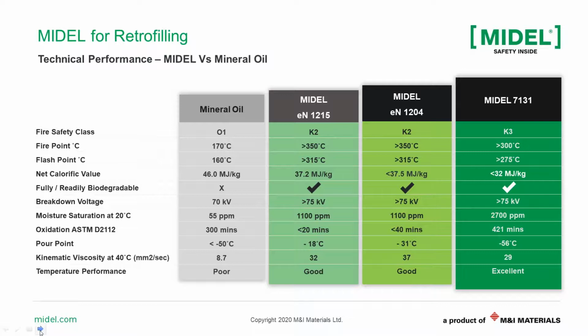The first one, as Steve mentioned, is about the fire safety of the liquids. As you can see on the screen, MIDEL has the classification K2 or K3, which means the fire point of these liquids is greater than 300 degrees C, and it has a low net calorific value, meaning it cannot sustain burning if things happen, and it has self-extinguishing properties.